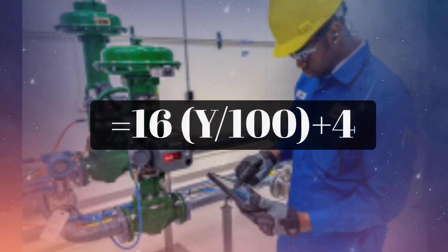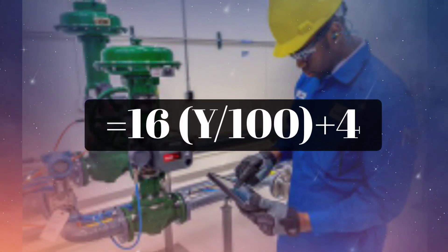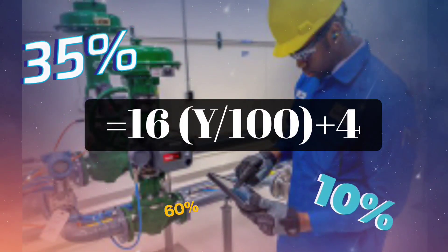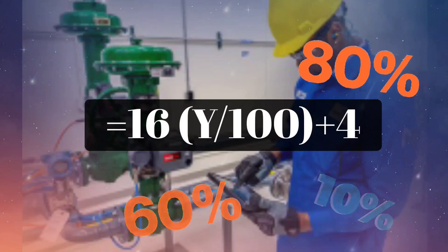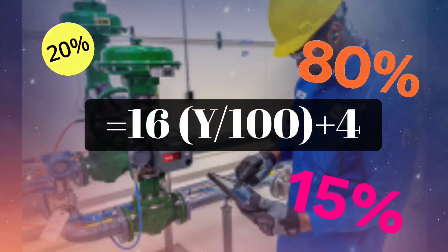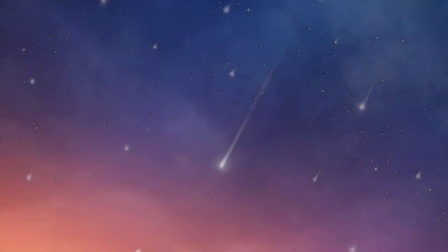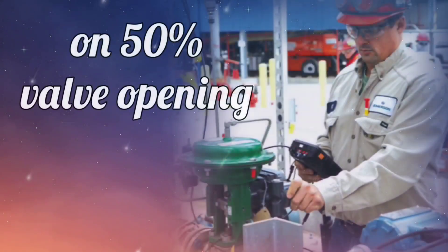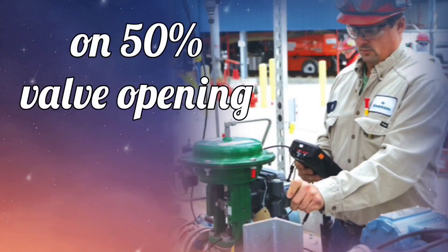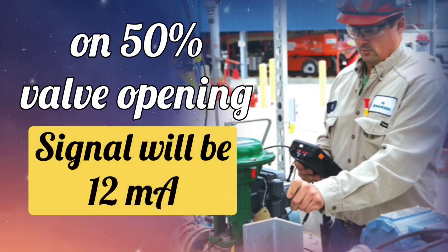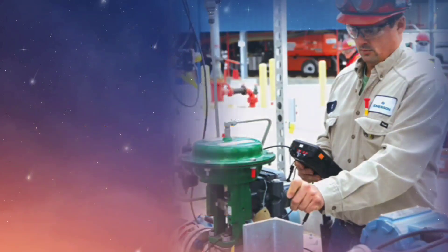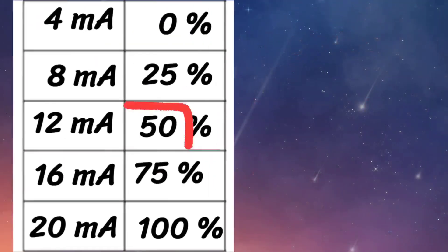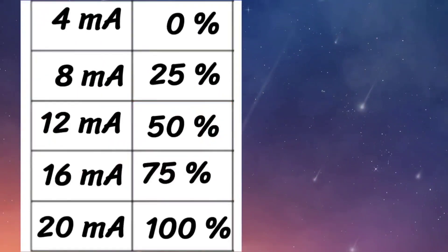So you can use this formula to check milliamperes at any percentage. For example, at 50% valve opening, 12 milliampere signal will be there. This is what we saw in the table.